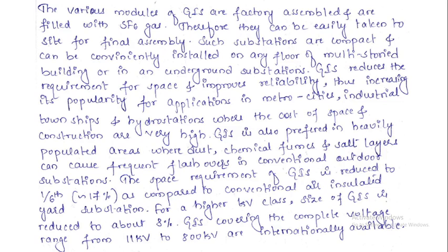Okay, gas insulated substation is also preferred in heavily populated areas where dust, chemical fumes and salt layers can cause frequent flashovers in conventional outdoor substations. Heavily populated area means there are industries or more and more vehicles running. So in those areas it may affect, as these air insulated substations are directly exposed to the environment. Because of all these dust, chemical fumes or salt layers, frequent flashovers are created in the conventional substation. So in order to avoid all these problems, we are going towards the gas insulated substations.